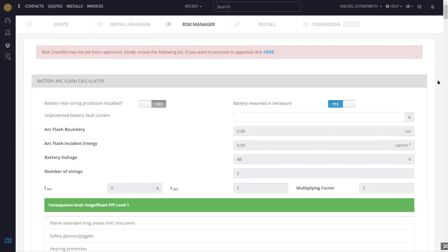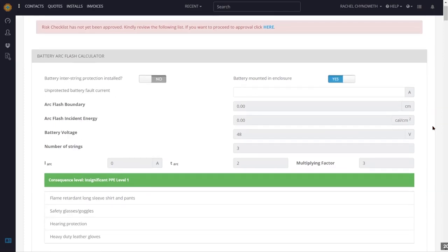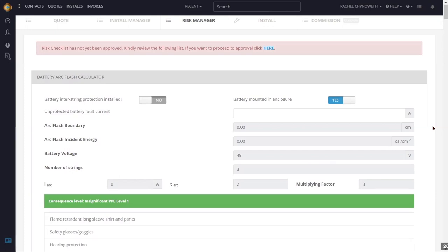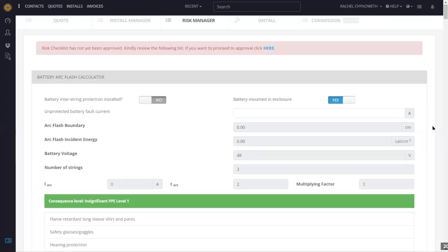Can you add your own documents to the user manual, such as safety certificates or NOCs? Yes, you can. This is the risk management section. We have the arc flash calculator here, and a checklist that picks up the specific battery and battery chemistry for the system — it's system-specific. Solar Plus responds to changes in safety standards and reflects that here, so your documentation is compliant. The arc flash calculations from a spreadsheet I previously produced are now embedded into Solar Plus — it does it for you using the data sheet for the particular battery you select.